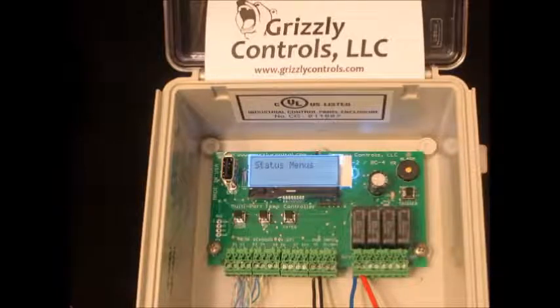The unit can be powered from 2 different sources. It can be powered from 12 to 24 volts VAC. So if you have a 24 volt VAC type system already installed and you want to replace it, this unit can handle that input voltage for powering. It's also got a DC input that'll range from 10 to 32 volts DC. So it has a wide range DC input as well.